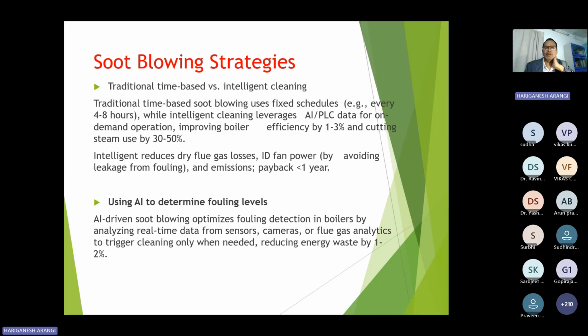Next comes soot blowing. Soot blowing is used to clean the boiler tubes. When the fuel is burning, there will be ash. That flue gas ash will be accumulated on the tubes at several places inside the furnace area, superheater zone, economizer, APH area. So this ash should be cleaned at regular intervals with the soot blowing process. Even this soot blowing process, if it is operating properly, improves the boiler efficiency by 1 to 3% and cuts steam use by 30 to 50%. So that much effect the soot blowing gives.